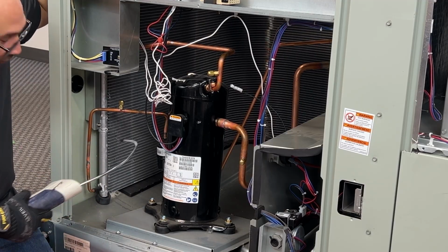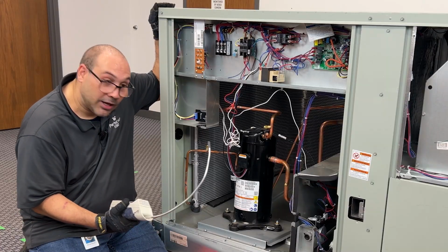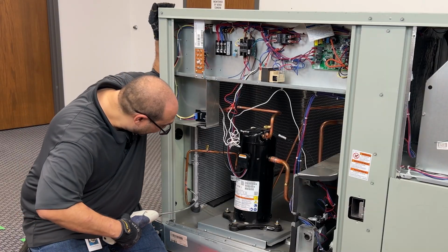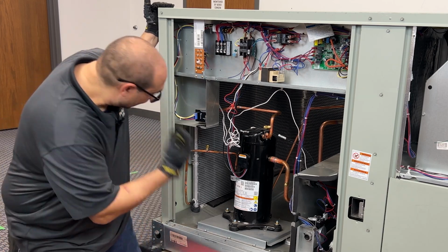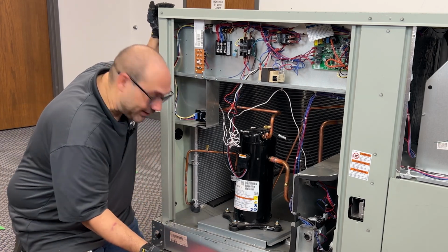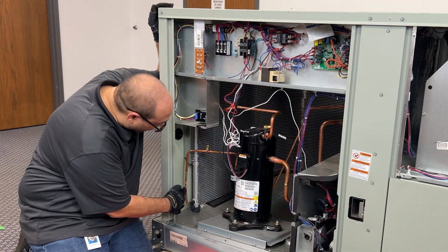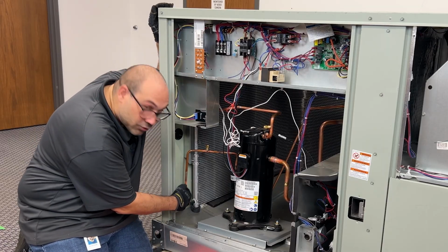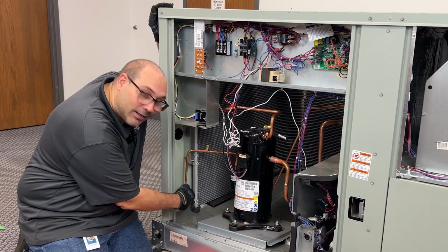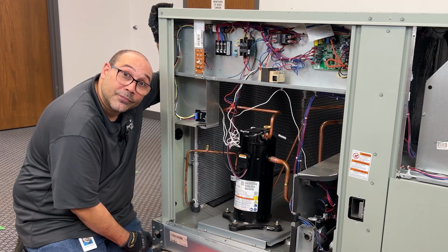So once you've identified, say the leak is here, I don't need to get an exact spot. I can put some soap bubbles on it if I need to. Otherwise, to be honest with you, if I look at this, I'm just going to heat up my torch a little bit and use that Sil-Fos that's on there and fix that leak.